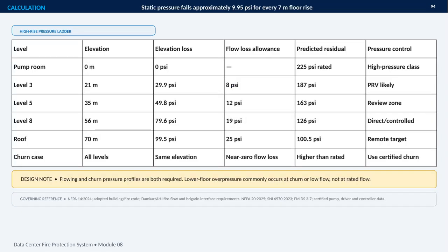This slide shows the pressure ladder for a high-rise fire protection system. The key calculation is that static pressure decreases by approximately 9.95 psi for every 7 meters of elevation gain. Starting with a 225 psi rated condition in the pump room, the predicted residual pressure declines to 187 psi at level 3, 163 psi at level 5, 126 psi at level 8, and about 100.5 psi at the roof.